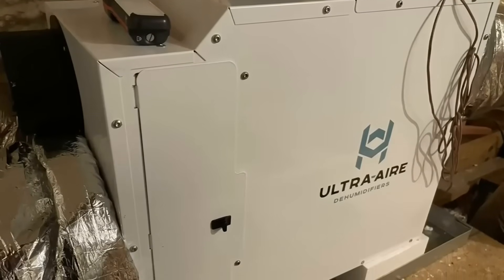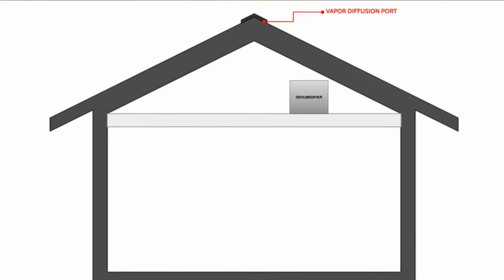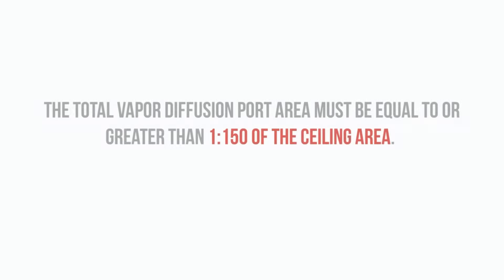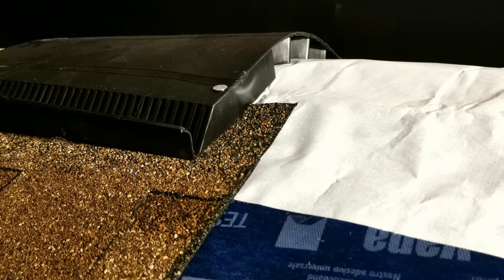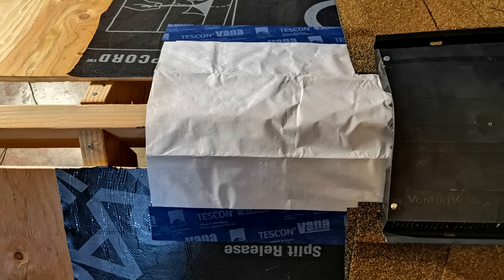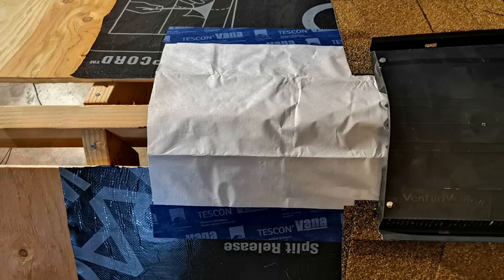This is just a belt-and-suspenders approach so that the vapor diffusion port is not challenged and so that you are operating at a reasonable interior relative humidity. Finally, in terms of ridge vent sizing, use a ratio of 1-to-150 diffusion port area to attic ceiling area. So if you have a 2,000 square foot ceiling, the total diffusion port area has to be at least 13.33 square feet. You can split that up across multiple ridges and openings, as long as it is installed at the highest points of the roof.